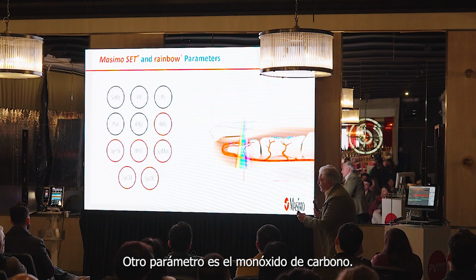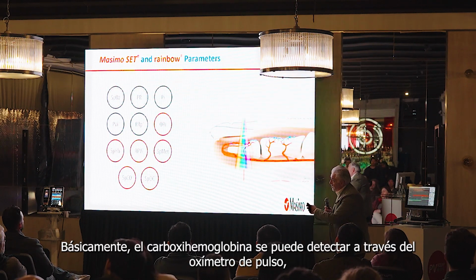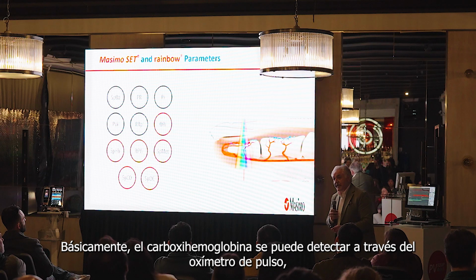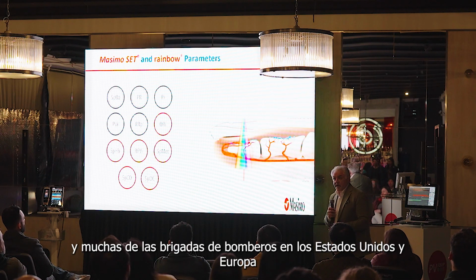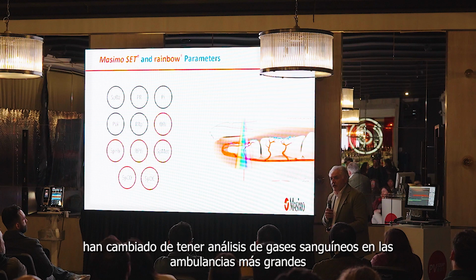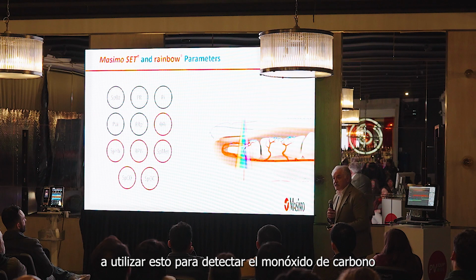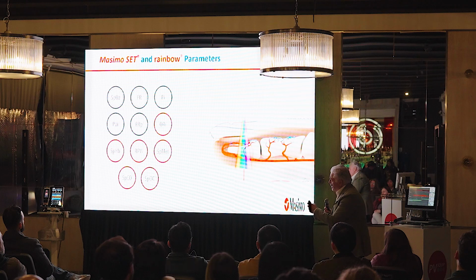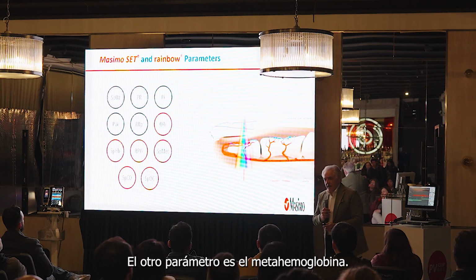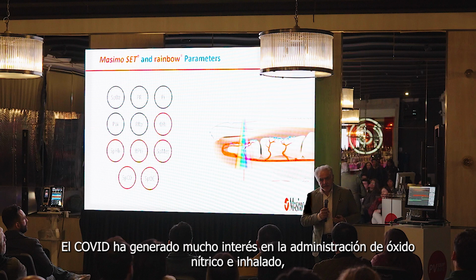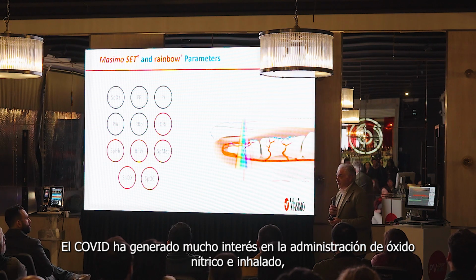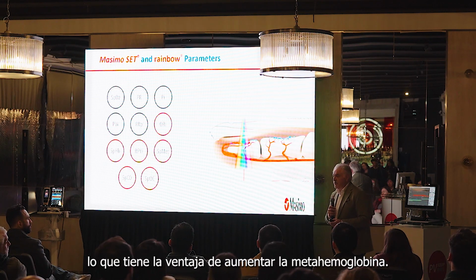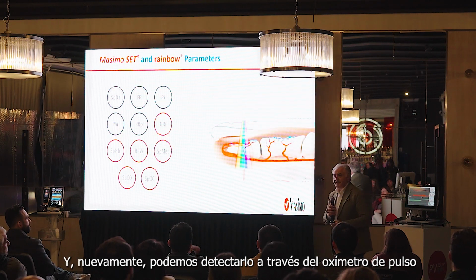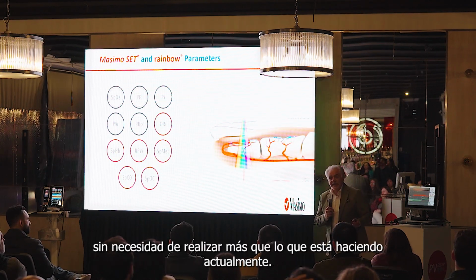The other is carbon monoxide. Carboxyhemoglobin can be detected through the pulse oximeter, and many of the fire brigades in the US and Europe have now switched from having blood gas analyzers, co-oximeters, in the ambulance to using this to detect carbon monoxide in patients who have been rescued from fires. The other one is methemoglobin. COVID has produced a lot of interest in giving inhaled nitric oxide, which has the disadvantage of increasing methemoglobin. Again, we can detect that through the pulse oximeter without having to do any more than you're currently doing.